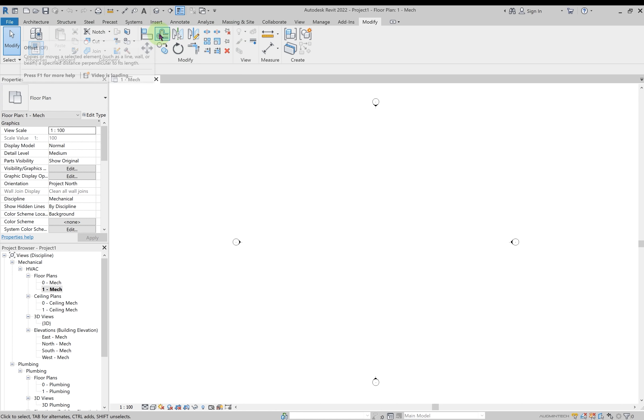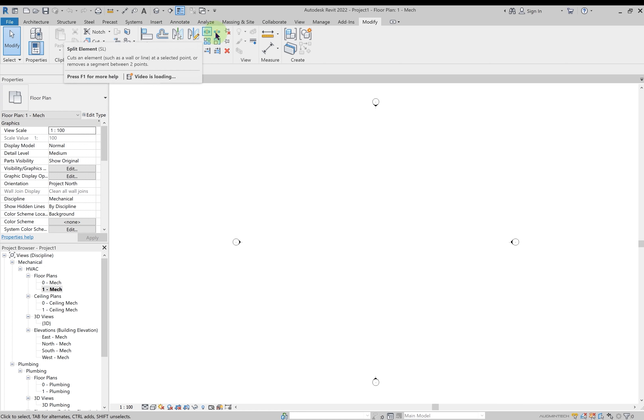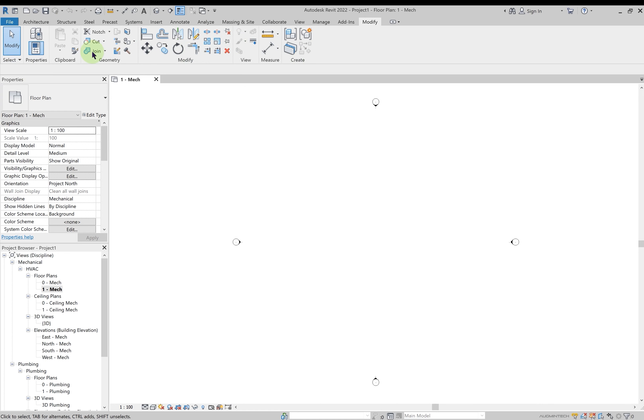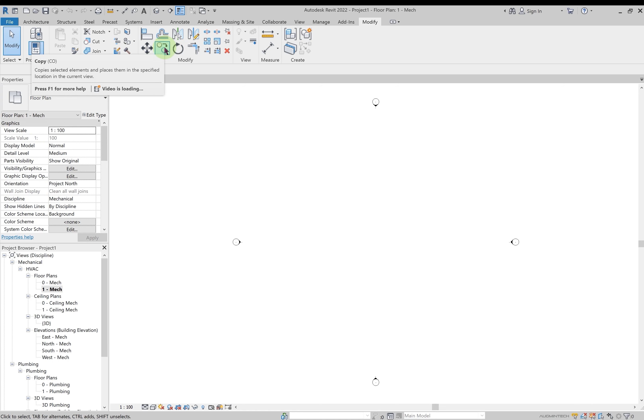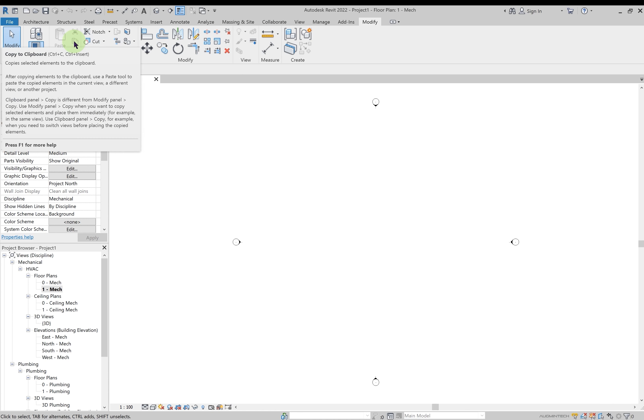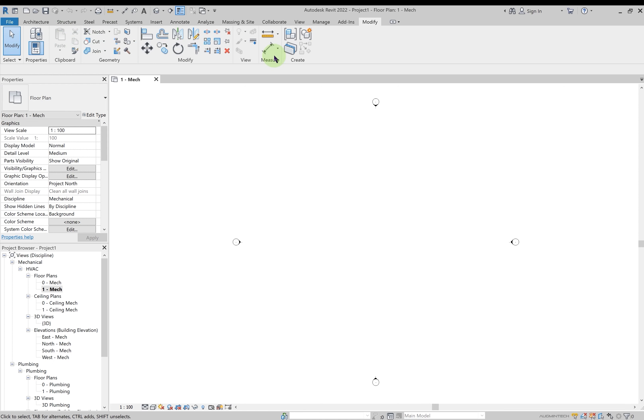In the Modify tab you can move, copy, rotate, trim, or extend elements. There is an important difference between two copy options. The regular copy pastes an element on the same level. But if you've created a duct system on the ground floor and want to copy it to the second and third floors, you must copy it to the clipboard first, then use the paste-to-level option. That's the difference between the two copy options.